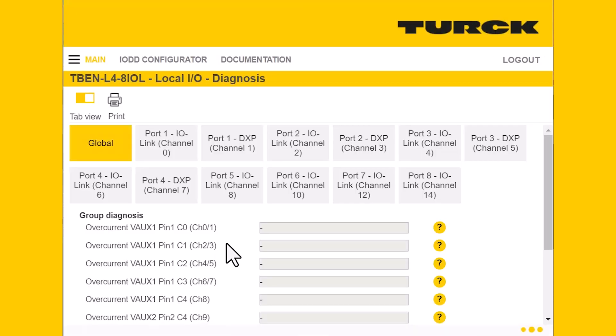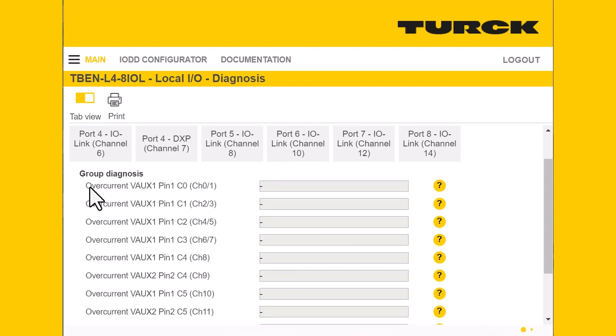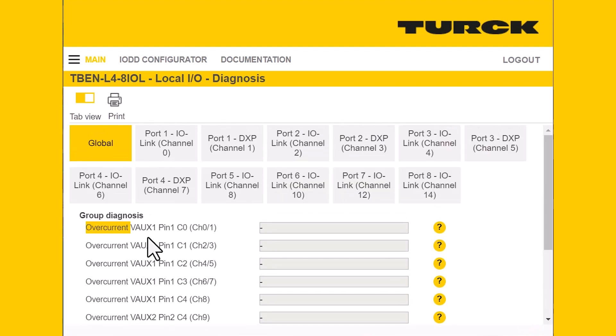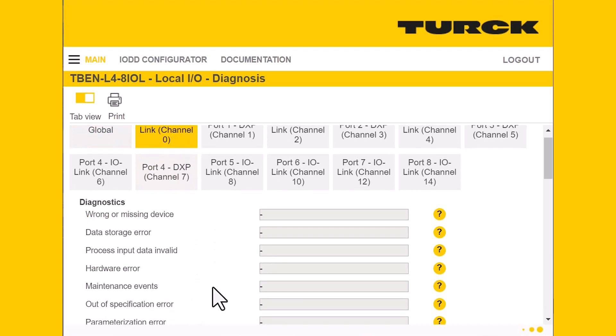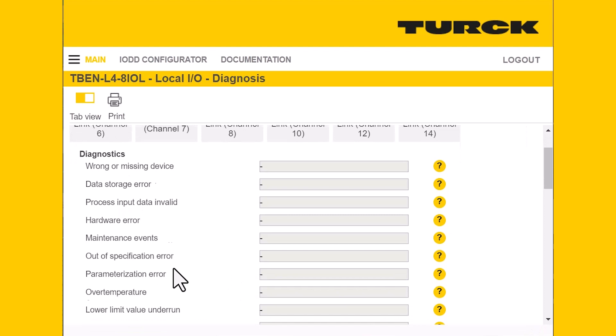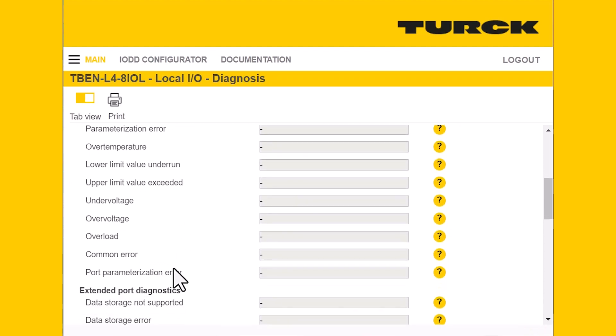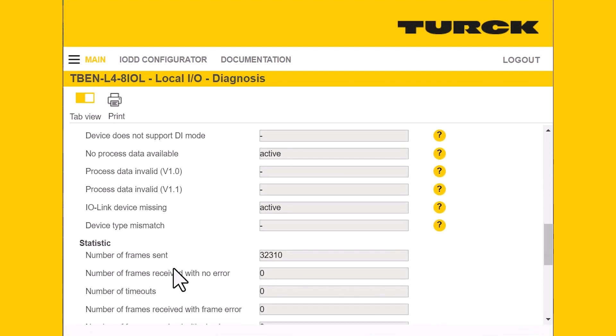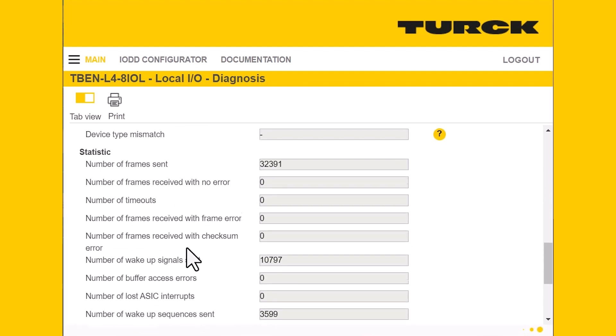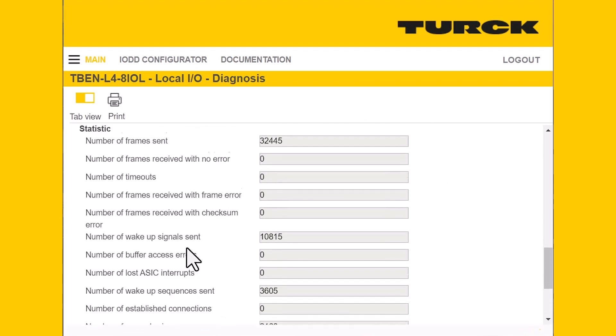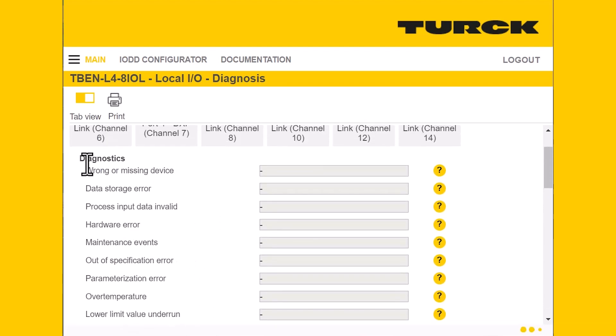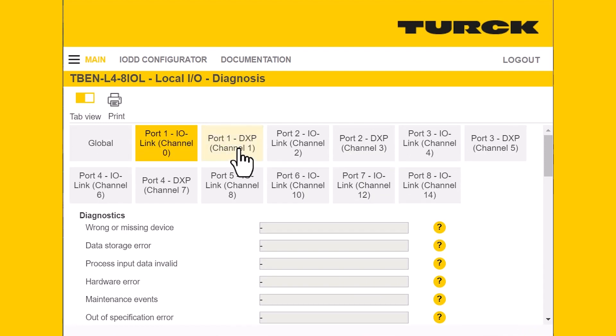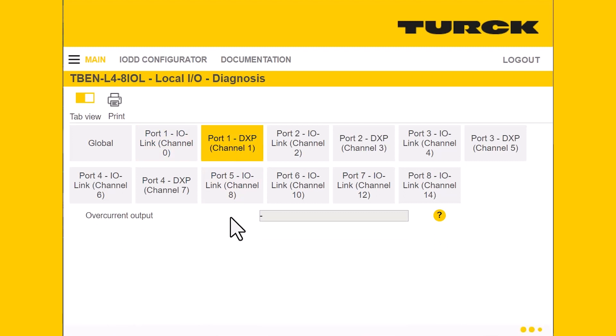Next, we'll go to the local IO diagnostics tab. For your global IO, it discusses your auxiliary pins and will let you know if there's an overcurrent on any of them. For your IO-Link channel, it'll let you know if there's a wrong or missing device, process data invalid, or a hardware error. There are many different potential diagnostics you can get from IO-Link, including frames sent, wake-up signals sent, and more. By far the most useful are wrong or missing device, parameterization error, and over-temperature. Your DXP pin will also tell you if there's an overcurrent at your output.